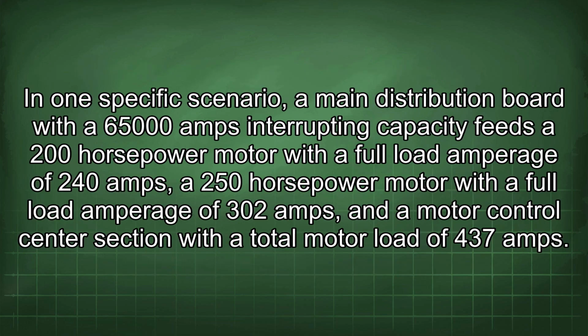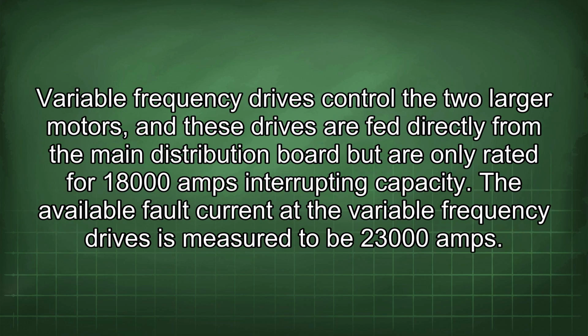In one specific scenario, a main distribution board with a 65,000 amps interrupting capacity feeds a 200 horsepower motor with a full load amperage of 240 amps, a 250 horsepower motor with a full load amperage of 302 amps, and a motor control center section with a total motor load of 437 amps. Variable frequency drives control the two larger motors, and these drives are fed directly from the main distribution board but are only rated for 18,000 amps interrupting capacity. The available fault current at the variable frequency drives is measured to be 23,000 amps.